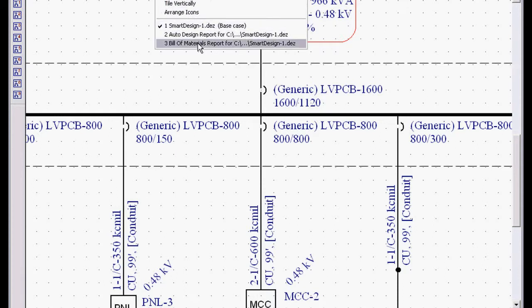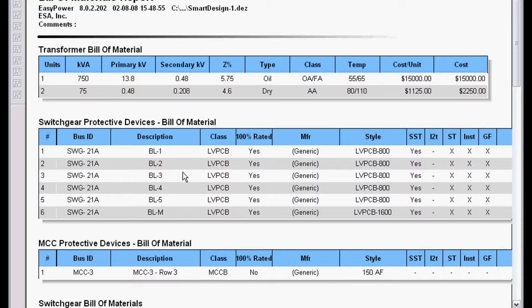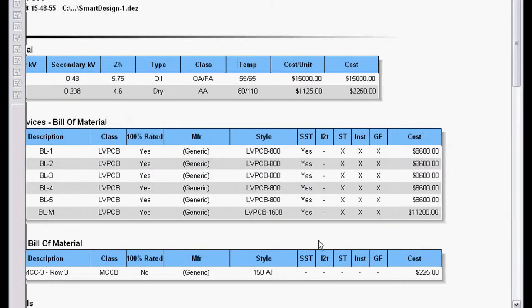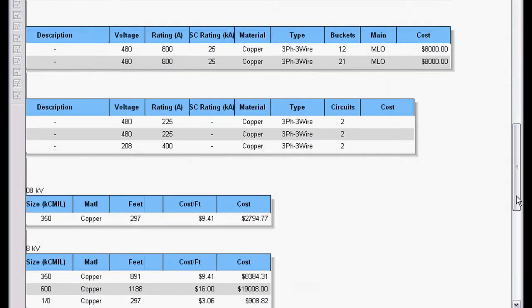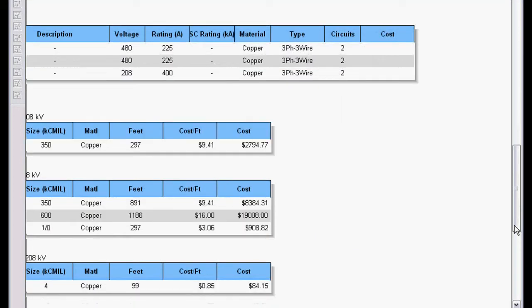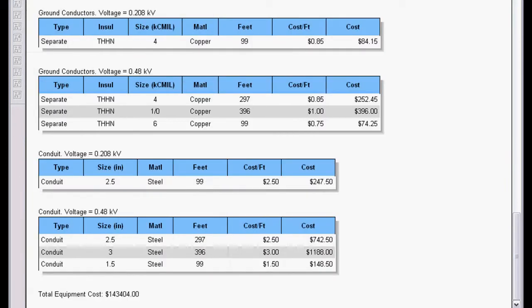And here's a complete system design with low voltage power circuit breakers. Let's go to our bill of materials and see how that affects things. As you can see, here's our bill of materials for the low voltage power circuit breakers with the various solid state trips, short time instantaneous and ground fault and cost. Now if we go to the bottom of the screen, you can see that jumped our cost from about $89,000 to $143,000.